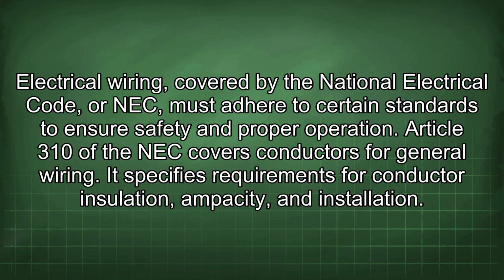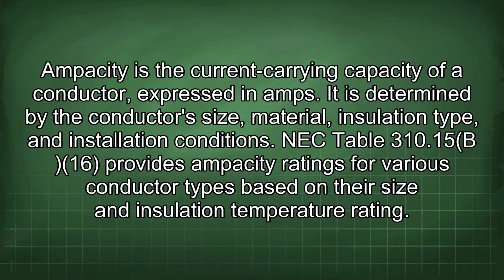Electrical wiring, covered by the National Electrical Code, or NEC, must adhere to certain standards to ensure safety and proper operation. Article 310 of the NEC covers conductors for general wiring. It specifies requirements for conductor insulation, ampacity, and installation. Ampacity is the current carrying capacity of a conductor expressed in amps. It is determined by the conductor's size, material, insulation type, and installation conditions.